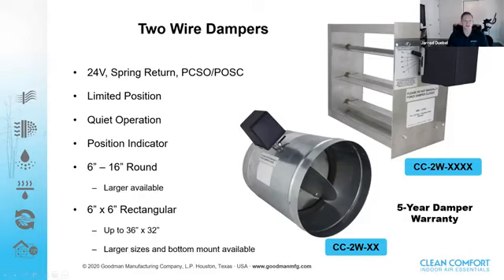They're insanely easy to remove and switch over. So if I need to change this round damper from power open spring return to a power closed spring open, there's this little Allen head. I loosen that up. I slide the damper motor off. I take it to the other side of the damper and I slide it on there. There's a little rubber grommet you've got to remove.